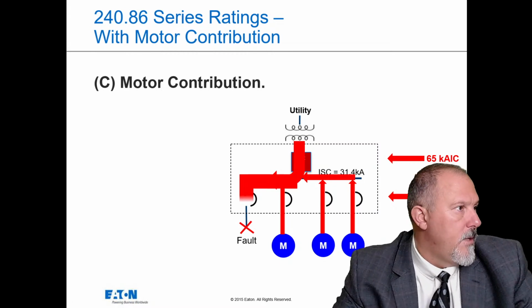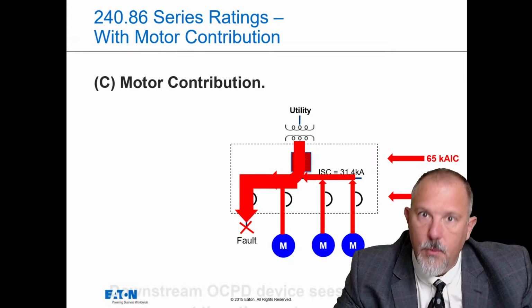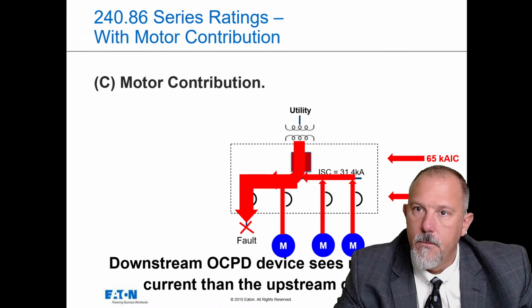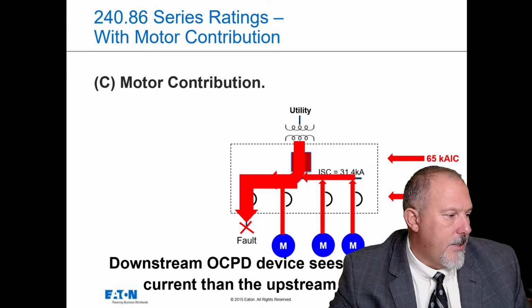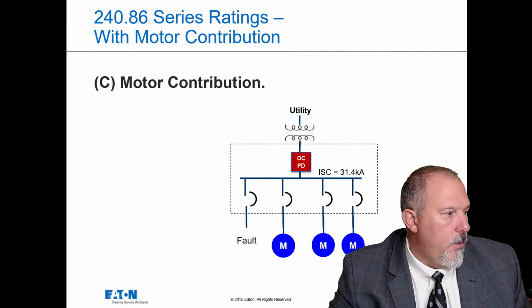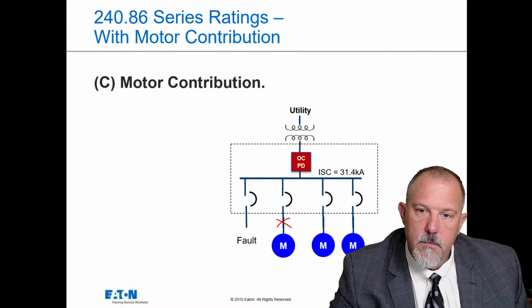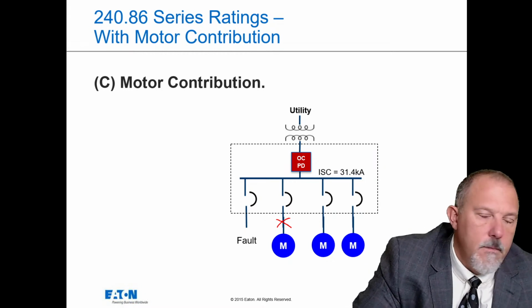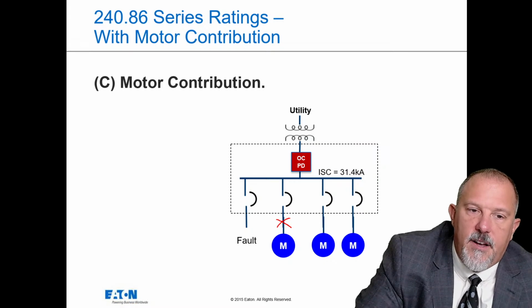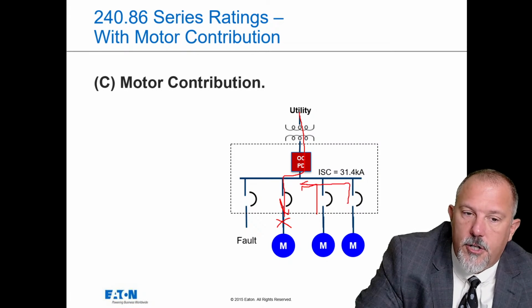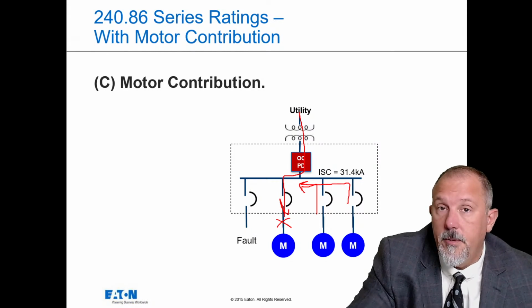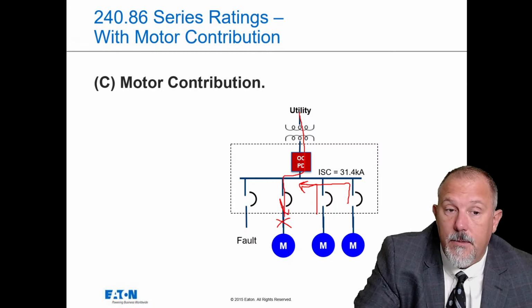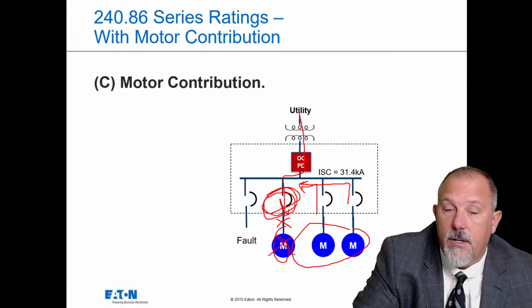And if, for example, I don't know if I can do this. I don't see why I can't do what I want to do here. So if, for example, I'm going to go back. So if my fault is here, so if my fault is there, I have utility contribution going to the fault. I have this motor contributing to the fault and that motor contributing to the fault. So I have those two motors contributing fault current, which if these two exceed 1% of the interrupting rating of this device, then, which if it's 10K, 100 amps, if these two motors exceed 100 amps, not this one, I don't have to worry about that one because it's downstream.